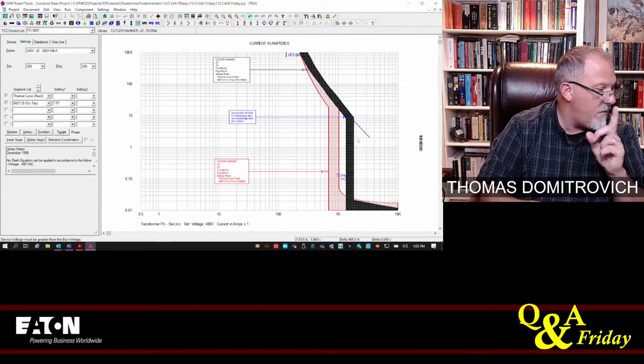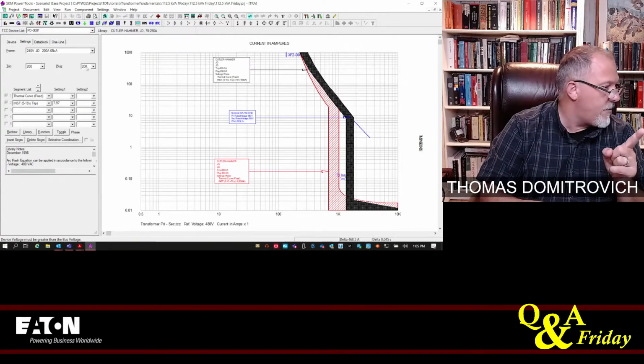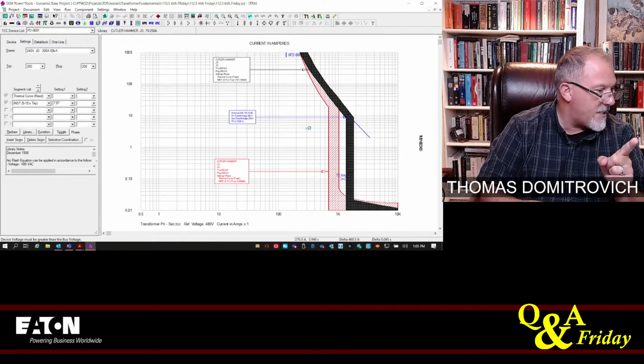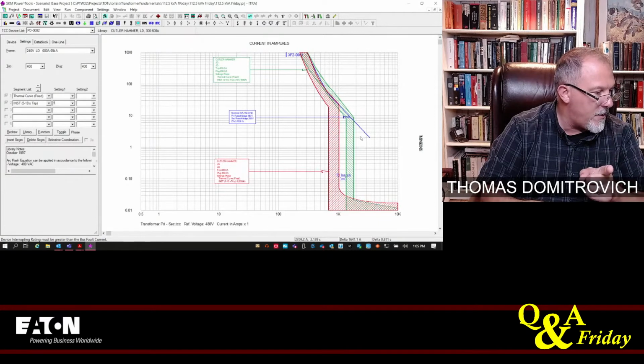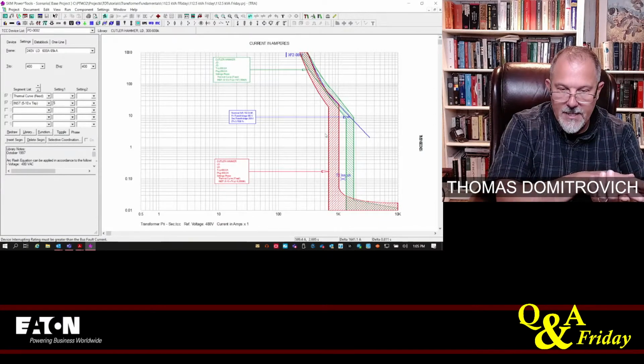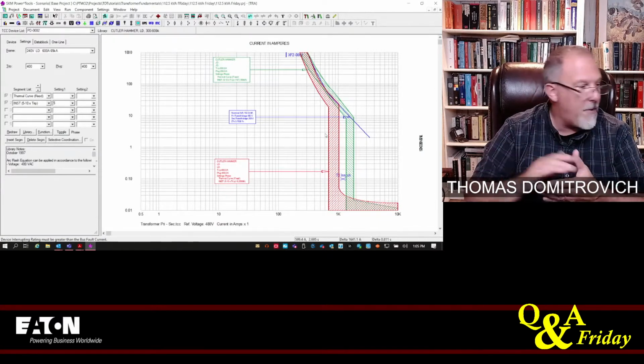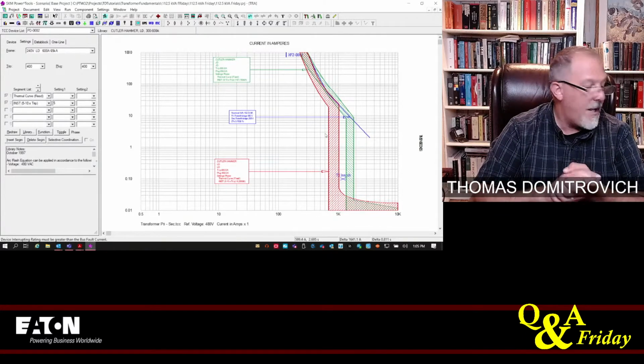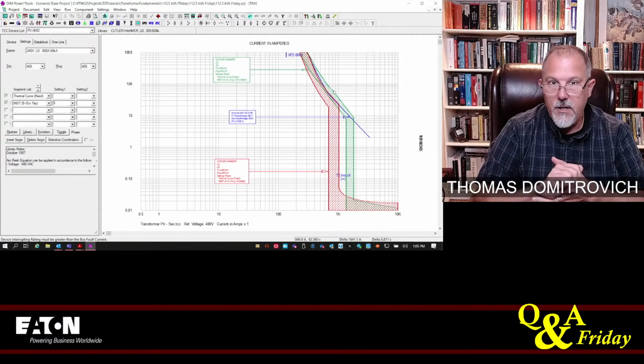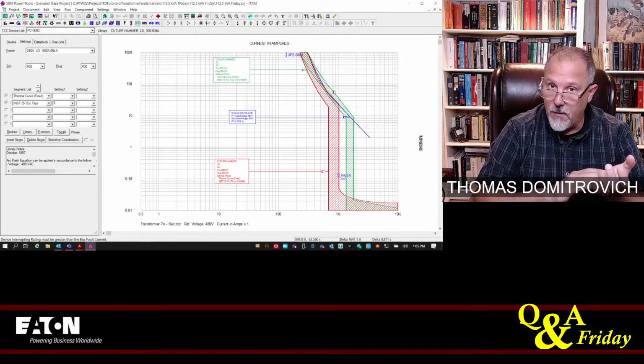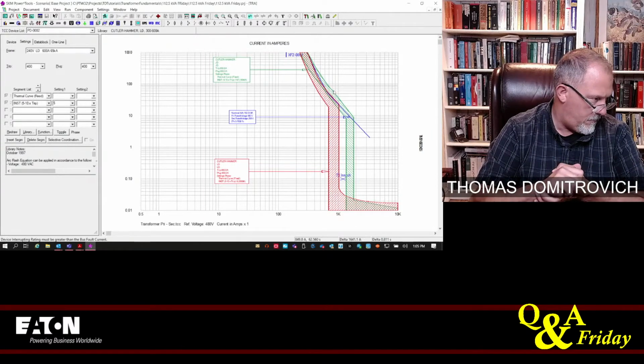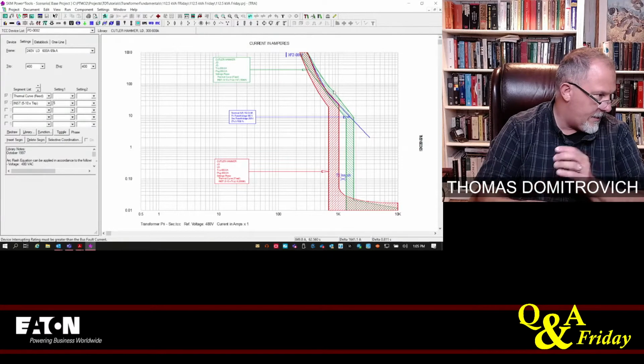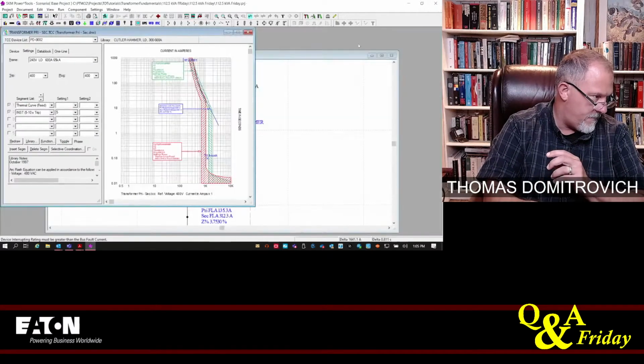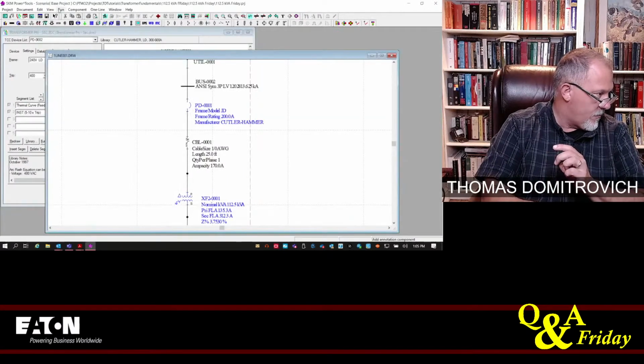All right. So I picked that breaker, that's the primary breaker. Secondary breaker works fine. Those are both thermomagnetic circuit breakers. I got a 400 amp on the secondary, 200 amp on the primary, and they're both thermomag. I'm providing adequate protection for the transformer. And let's run an arc flash study. So I go to run.